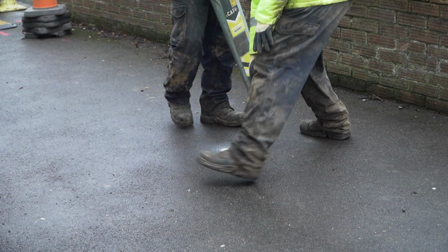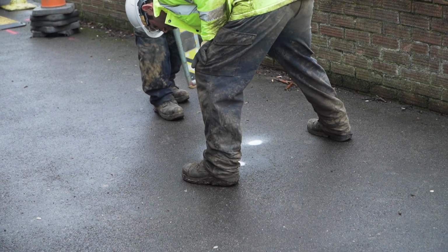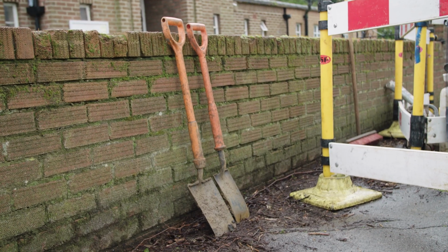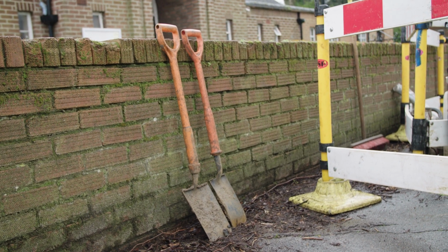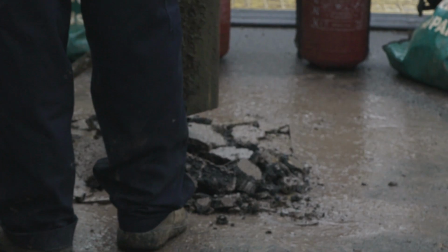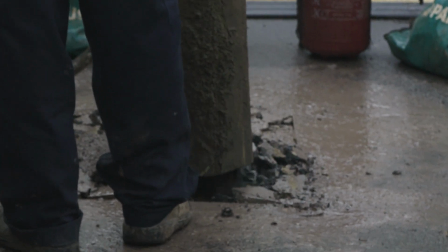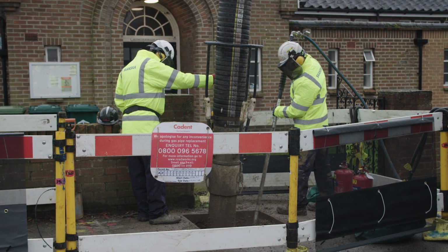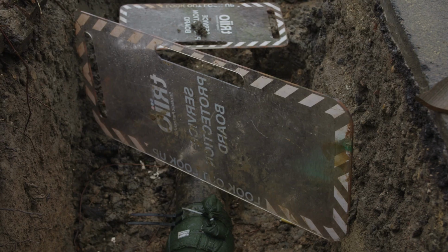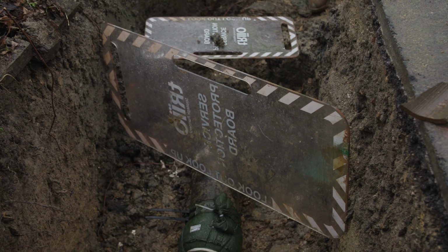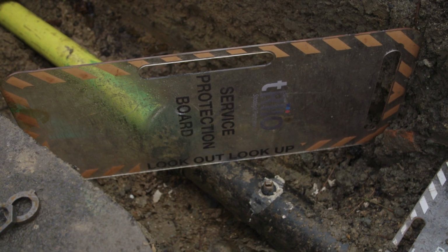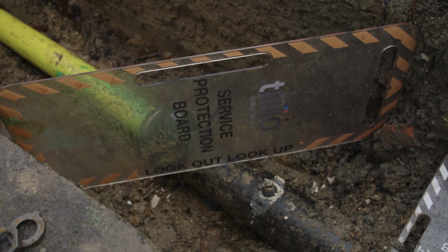Before digging starts, the construction team must perform a fresh CAT and Genny survey to verify any prior markups. Hand-dug trial holes must be used to confirm the location of the underground plant. The first choice of excavation is vacuum or air-based techniques. These methods are very effective in avoiding utility damage and also create other efficiencies, as well as reducing the manual handling risks. Excavators should not be used within encroachment lines of buried services, unless a physical barrier and safe system of work has been established to protect the asset.